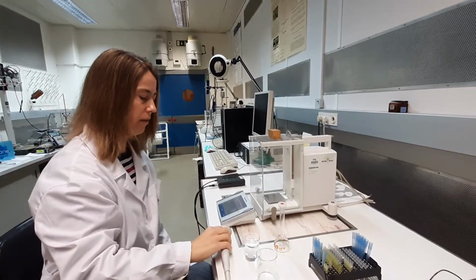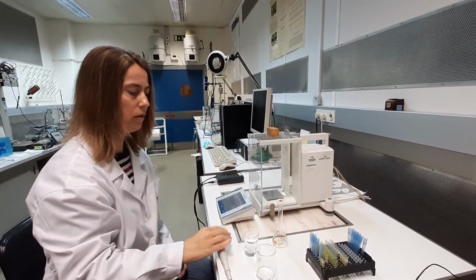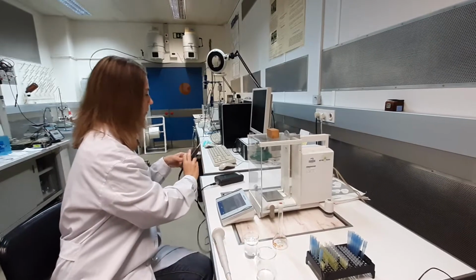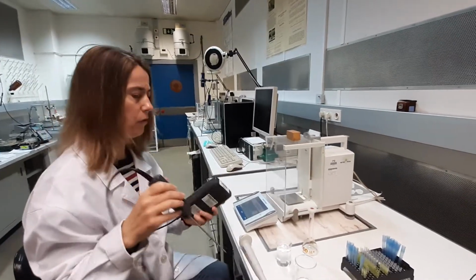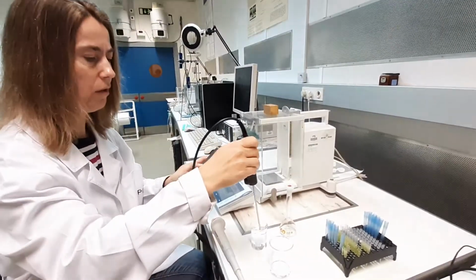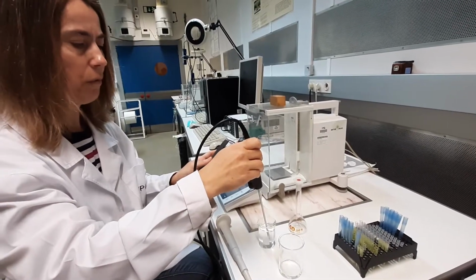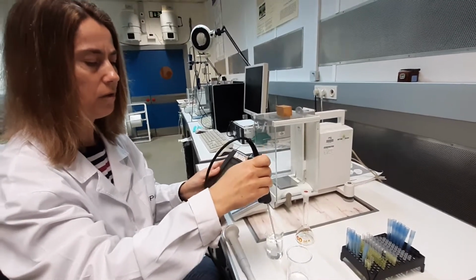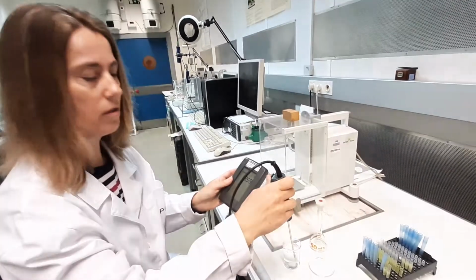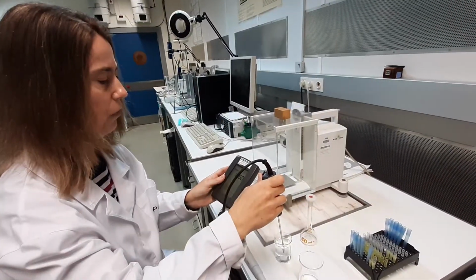So before we start the calibration, we need to measure the water temperature. So we use a temperature sensor or thermometer, whatever you wish, and we measure the water temperature. And this will be used later on for the calculations of the delivered volume. So we have our temperature.